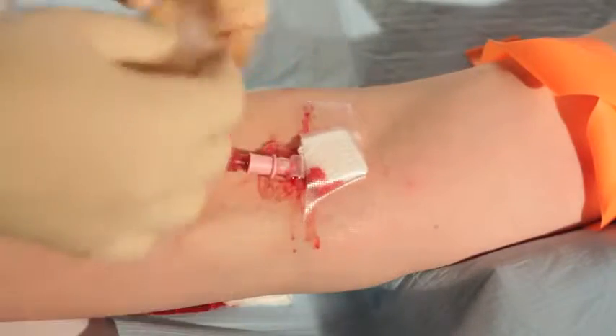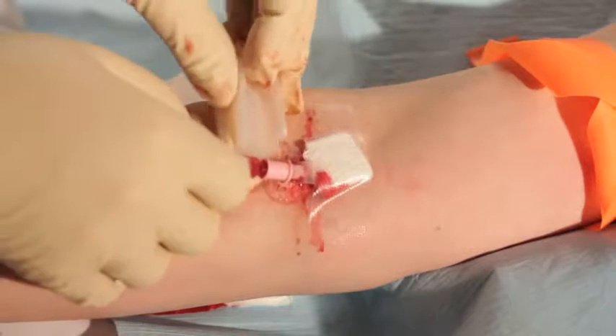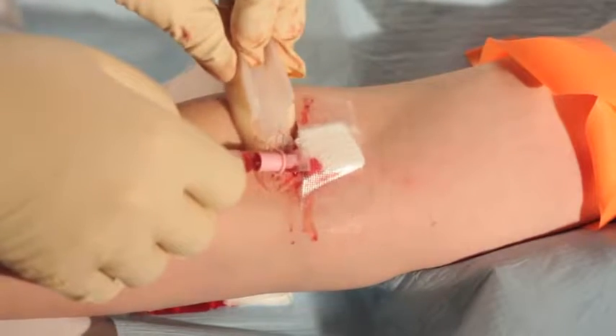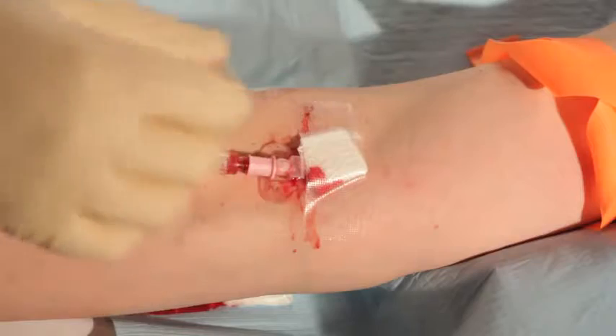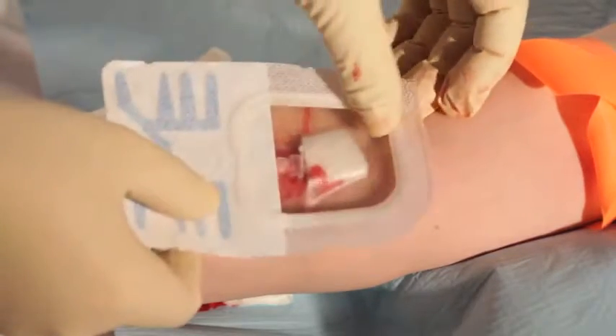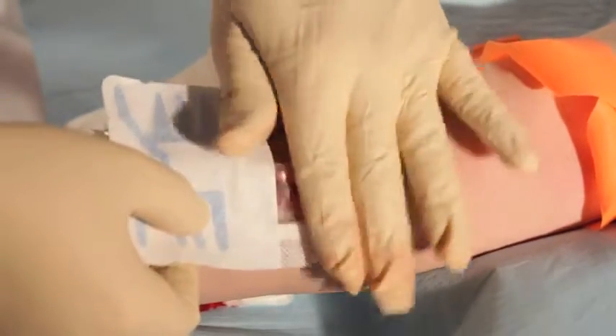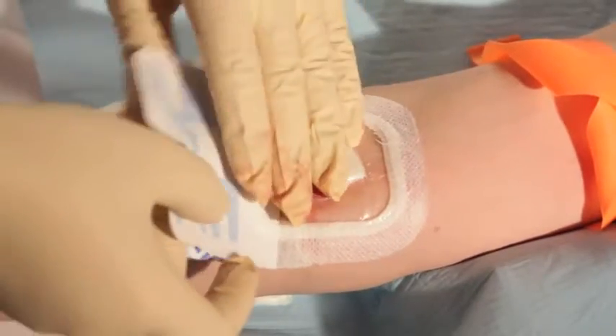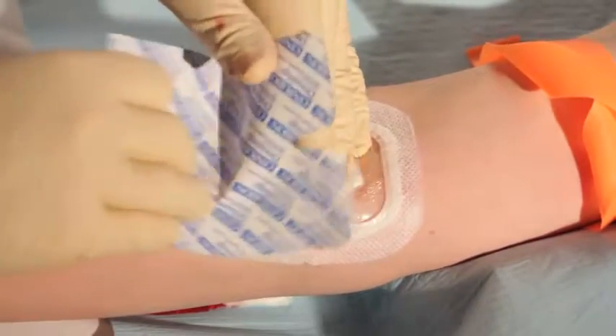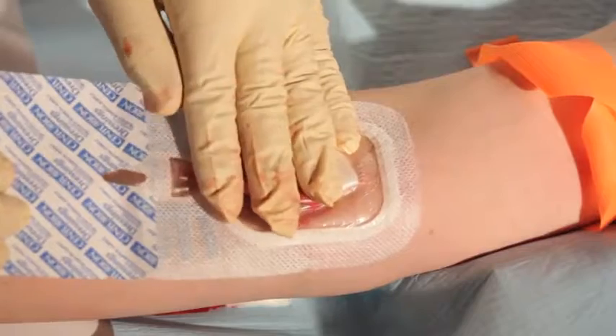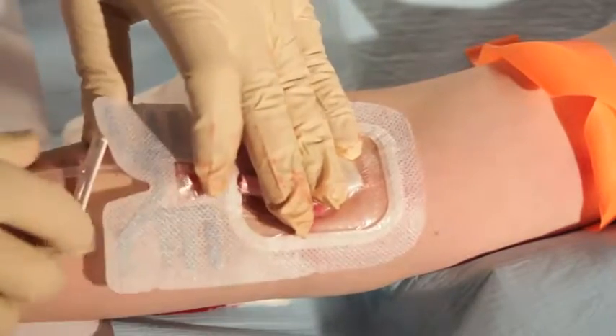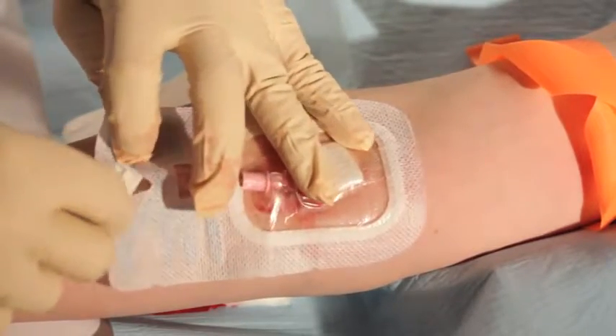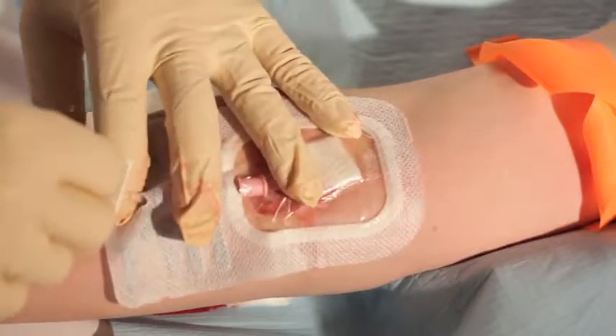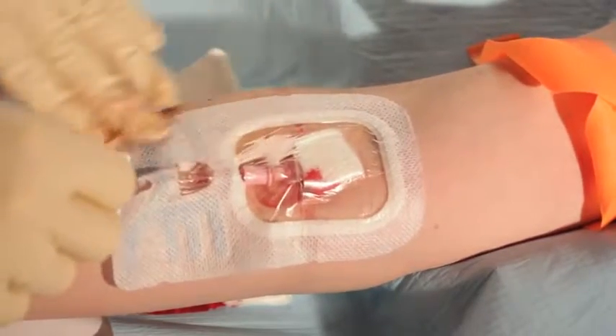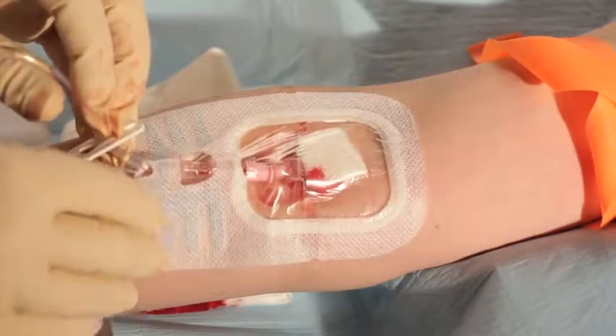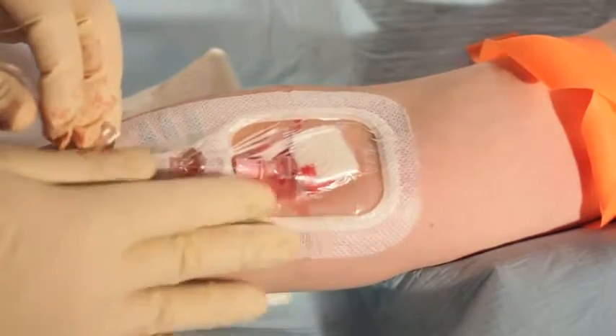Catheter securement and dressing is a matter of institutional policy and typically involves application of the securement device and a transparent dressing, such as the SorbaView shield. To properly use the shield, peel the upper backing off the large window on the dressing. Center the window over the insertion site. Press down on all sides of the dressing until it is secure against the skin. Remove lower backing by pulling the tab down towards the extension set.